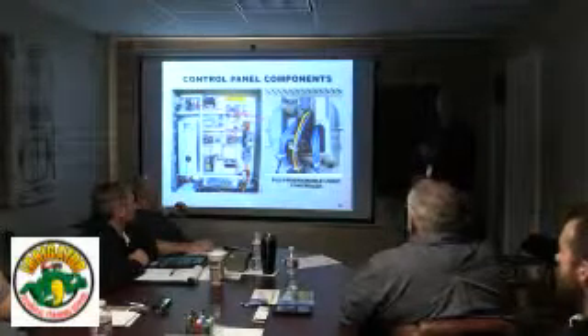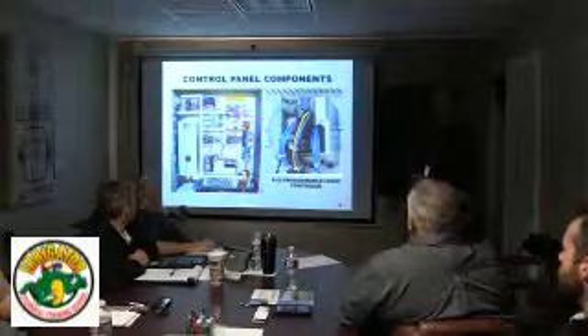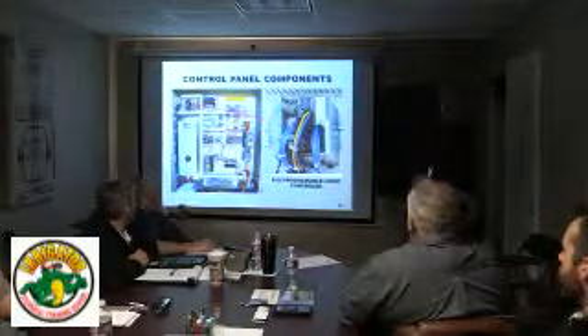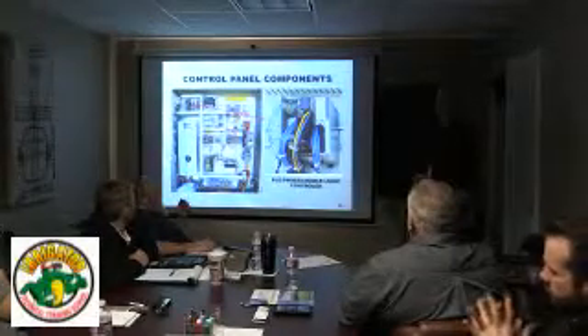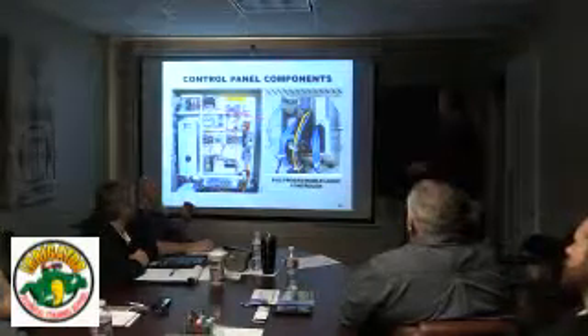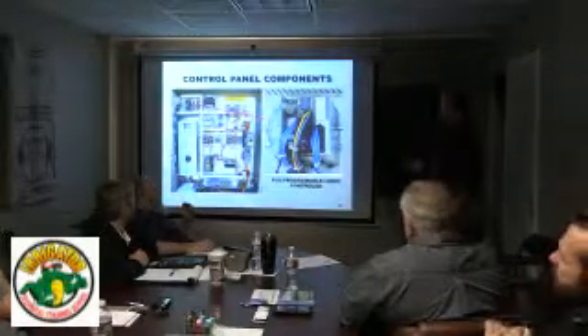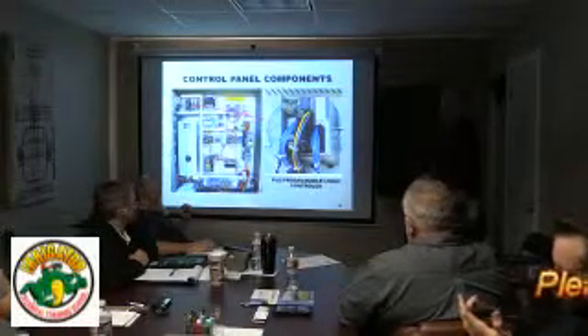You're going to have one of these wires coming from the hand side of the HOA, another one from the auto side, one coming from the high pressure switch, whatever it happens to be on there. If it's an input to the PLC, it's probably a blue wire. Here's those purple ones again. Like I say, it comes from the breaker up to here and then from here back out to there. So the PLC controls that solenoid valve that goes out to clear water screen.